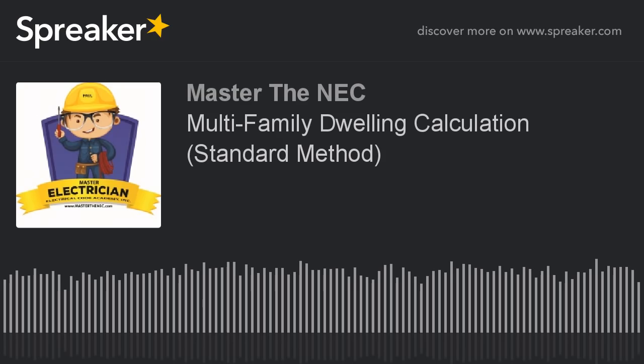Now, let's just move on down the list because that's just how it works. The next thing is 220.56, kitchen equipment, but we don't have any, and that's dealing with other than dwelling units. So when we get into commercial applications, that would come into play. So we don't use that here. The next one is 220.60, noncoincident loads.